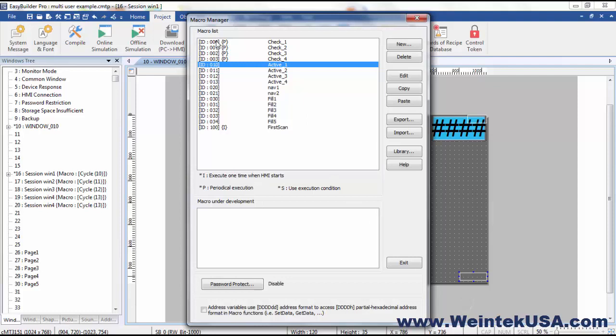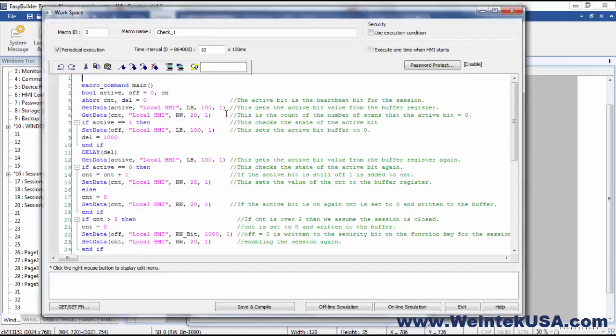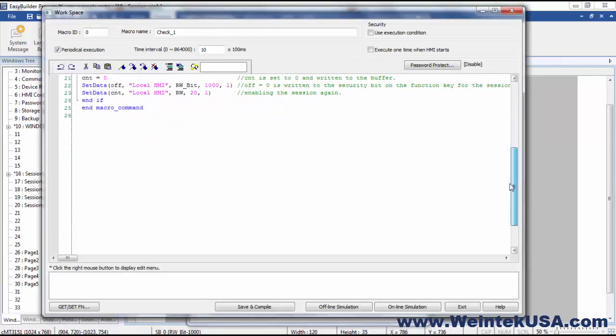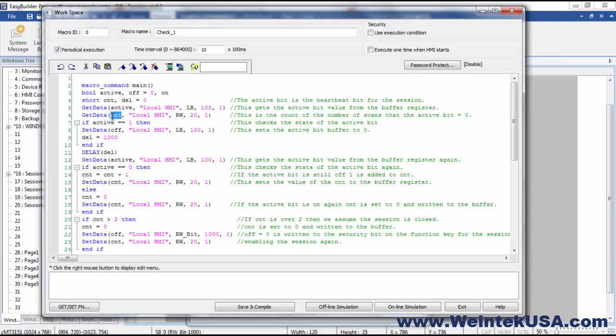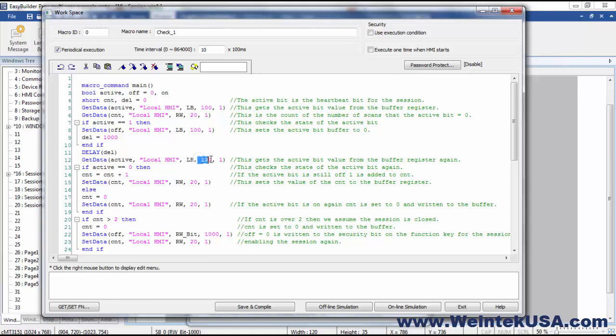Now, on a periodic cycle, this check macro is running, and what it's going to do is it's going to get the value of that heartbeat bit I was telling you about. This one is specific to session one, and it's going to get the count value that we have buffered in this register. And if the value of this active bit of our heartbeat bit is one, then we're going to go ahead and turn that bit off. We're going to write a zero into that same register. We're going to set a delay here, and then we're going to get that value again and see if it has been written back to one by the active macro.